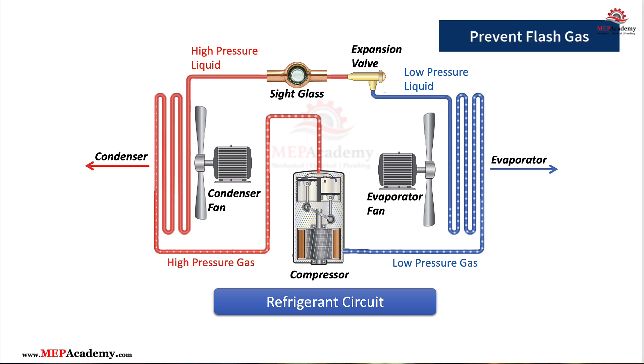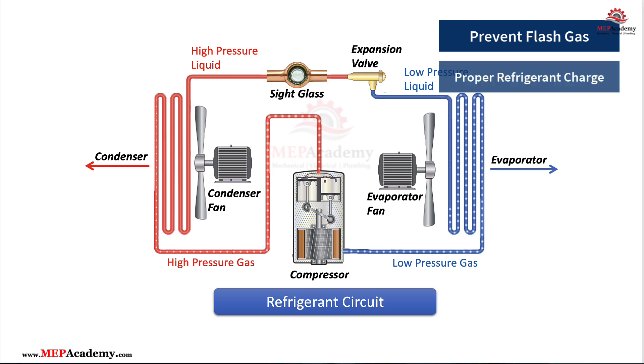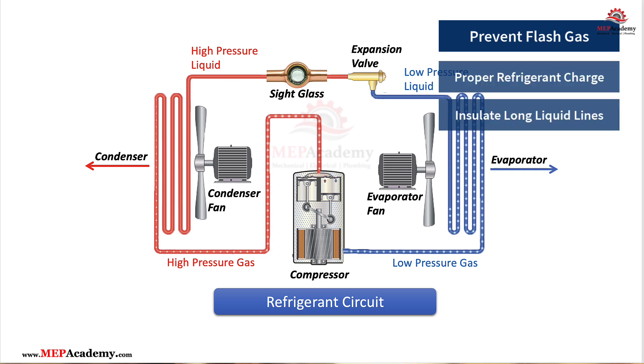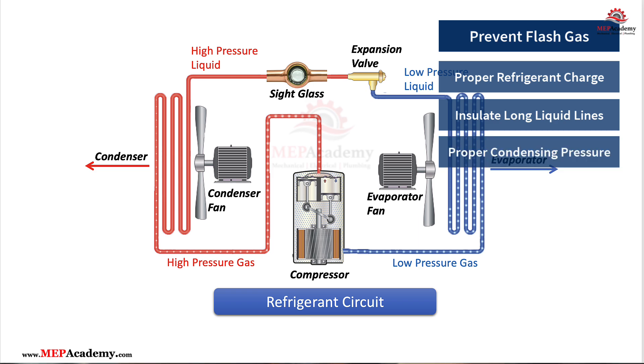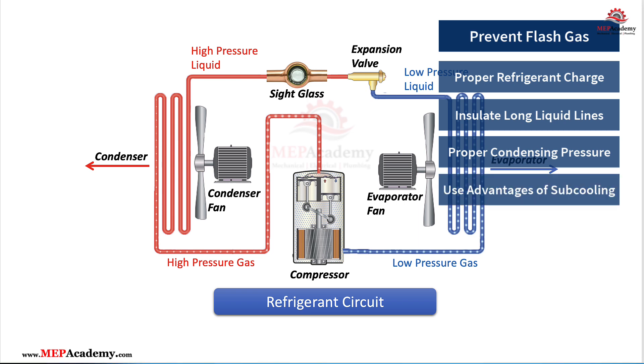To prevent flash gas where it shouldn't be, follow these best practices: 1. Ensure proper refrigerant charge. 2. Insulate long liquid lines in hot environments. 3. Keep condensing pressures within design range. 4. Use subcooling to your advantage.